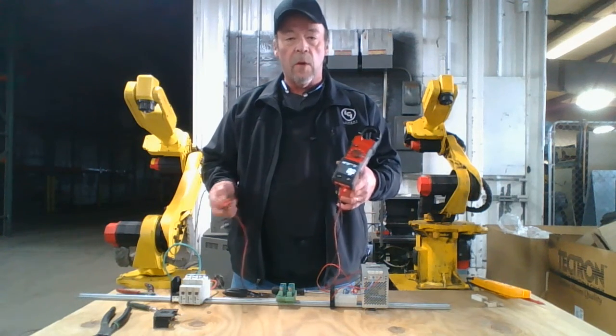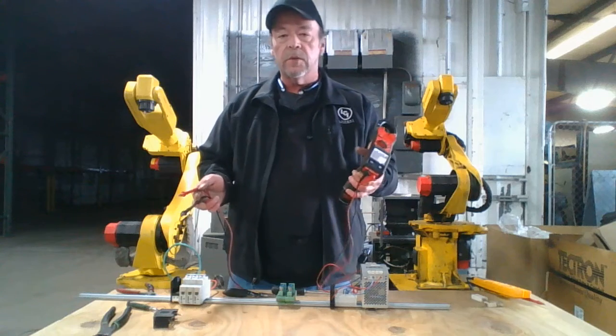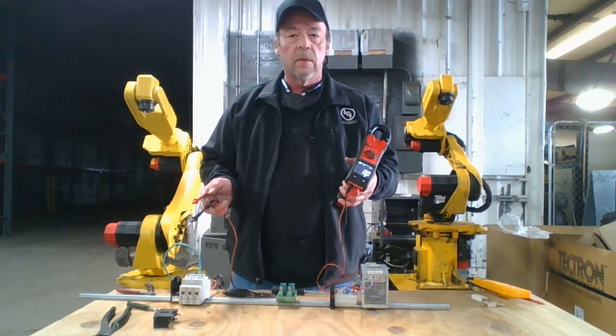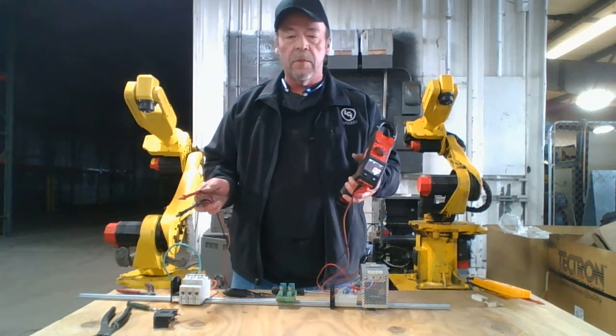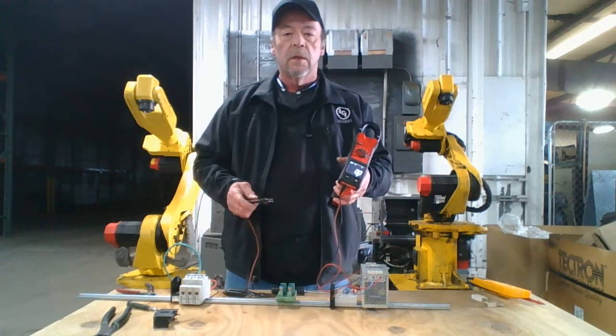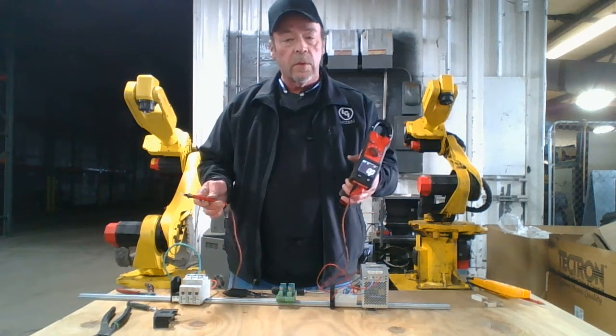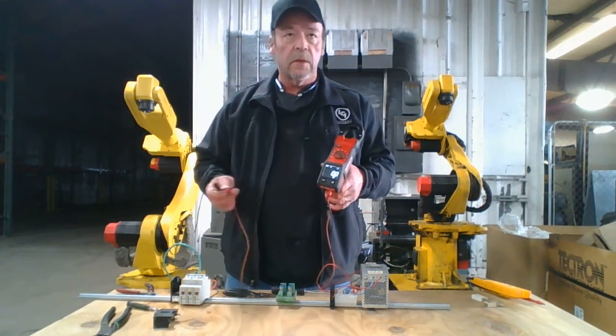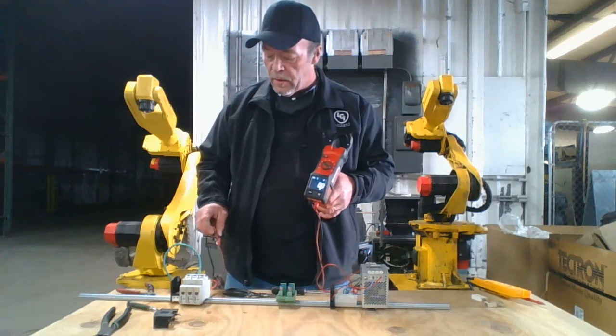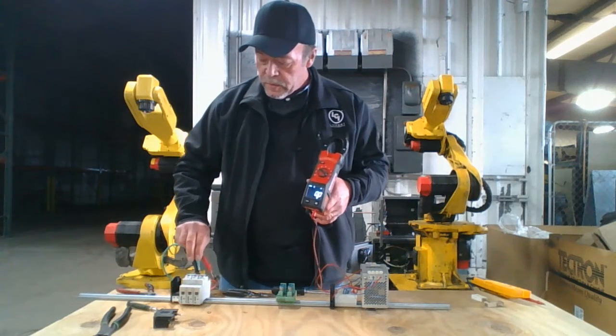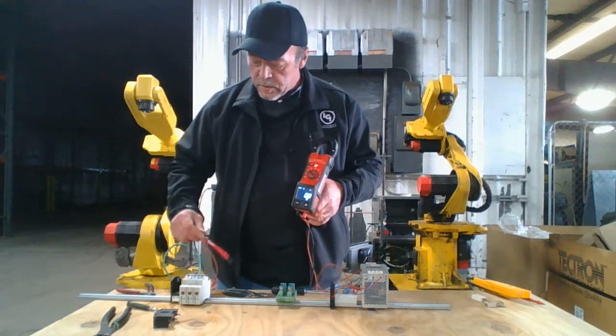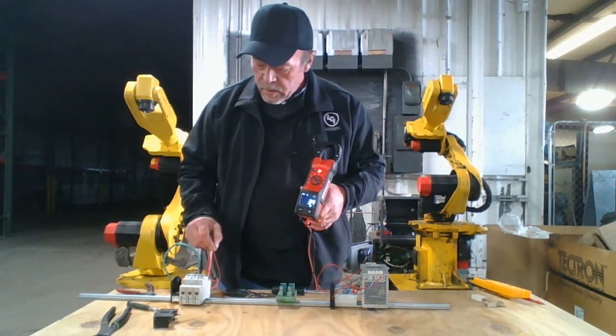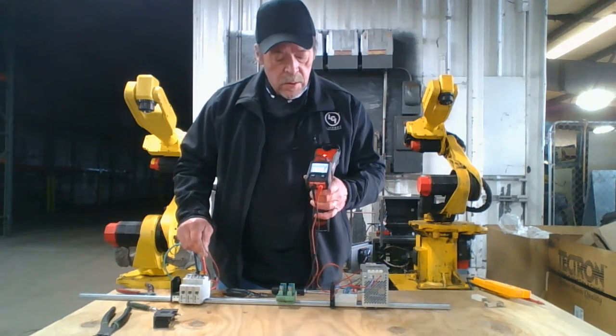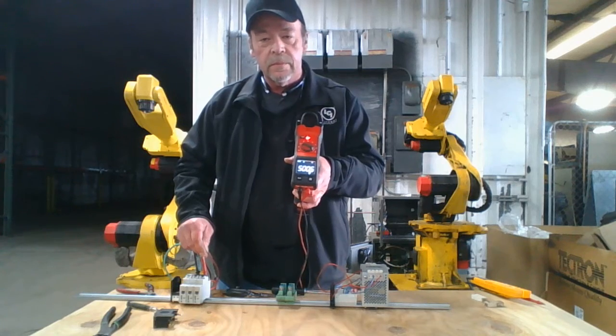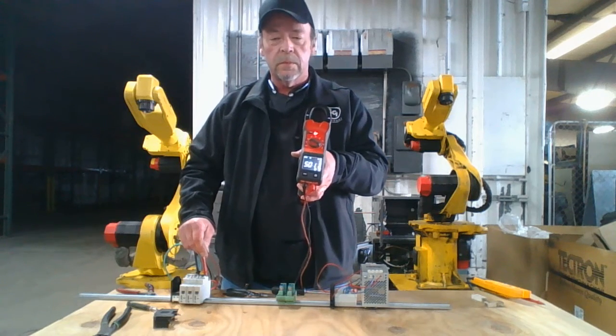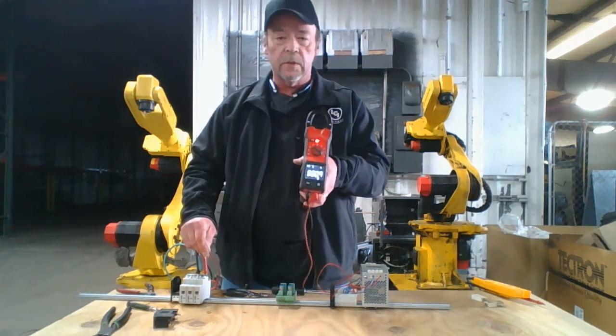you have to make sure it's wired delta. Delta is not used so much anymore. Most of the factories you'll be in will be Y. But some of the older buildings are still running delta, like this one. There again, when you check, you get 500 volts. You wouldn't even know that it was delta unless you check it to ground.